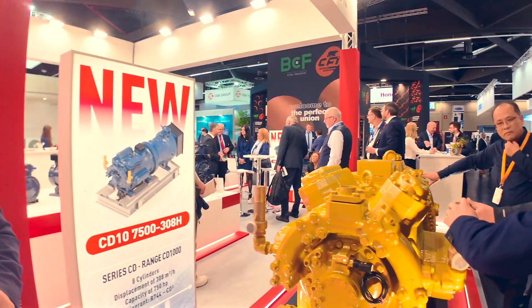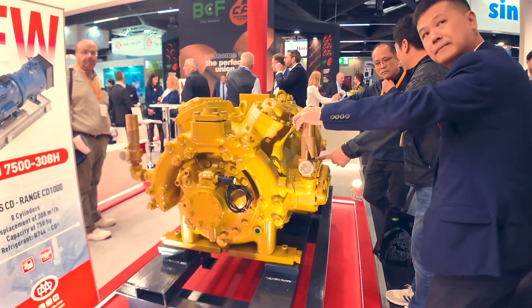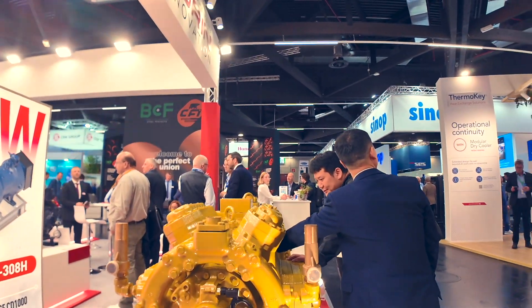This particular model on display is a semi-hermetic compressor. We have an open drive version as well. It's an eight-cylinder compressor with very large cylinders and pistons, and as I said it can develop up to 300 cubic meters an hour and 750 horsepower.